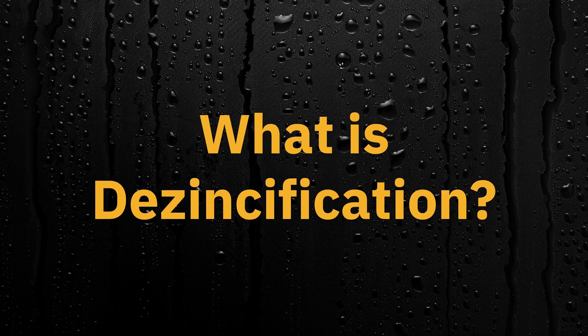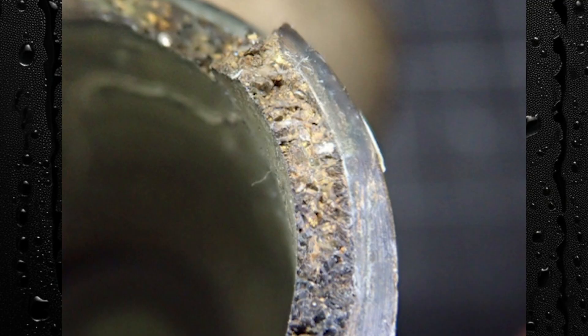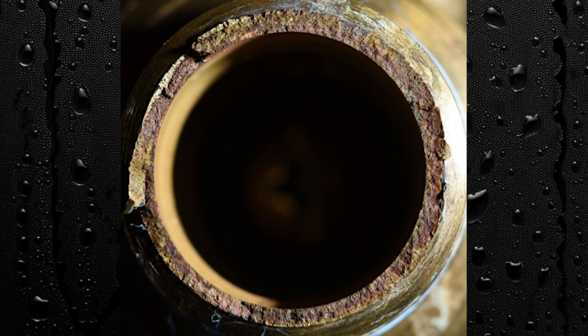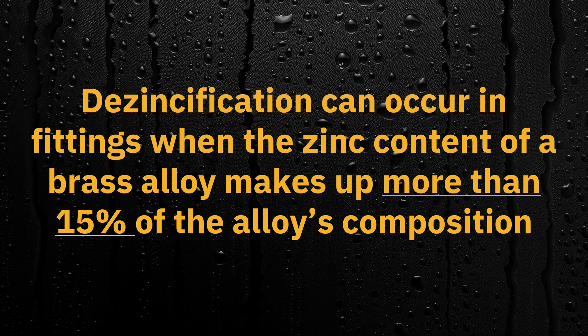So what is de-zinkification? Dezincification is corrosion that occurs to brass fittings when the zinc content of them is lost and copper is left behind in its place. This process can occur slowly over time and can lead to issues in your plumbing system. Dezincification can occur in fittings when the zinc content of a brass alloy makes up more than 15% of the alloy's composition.